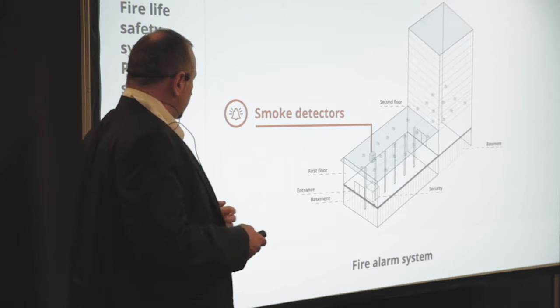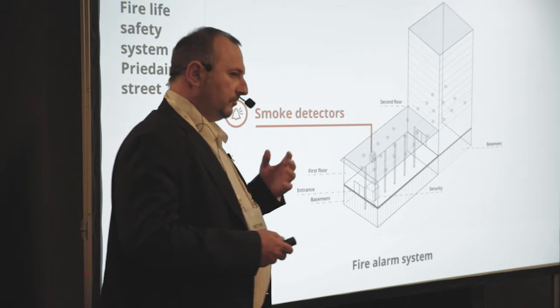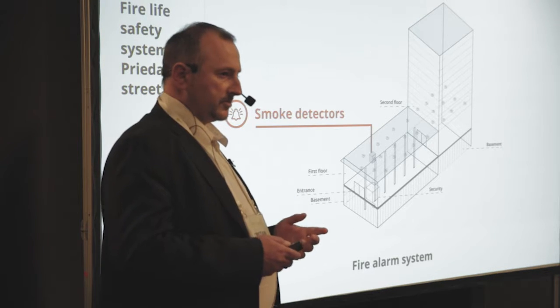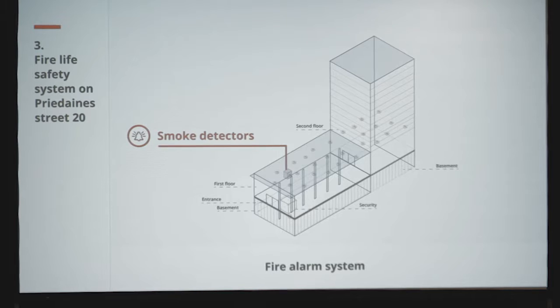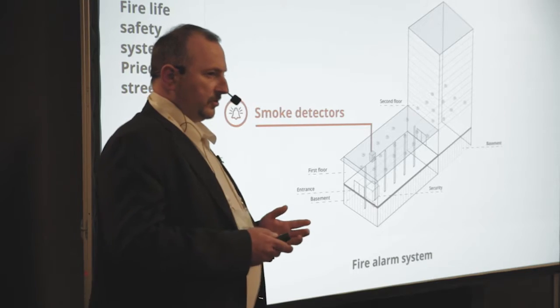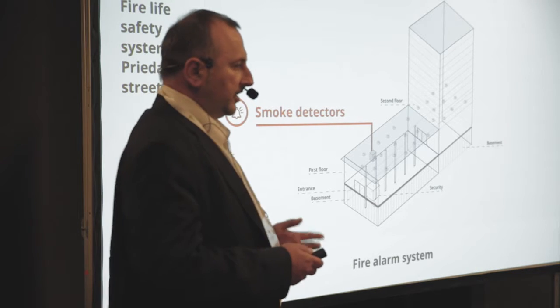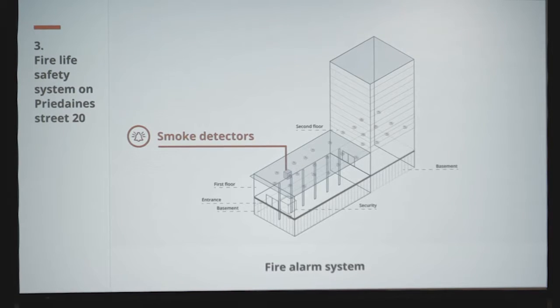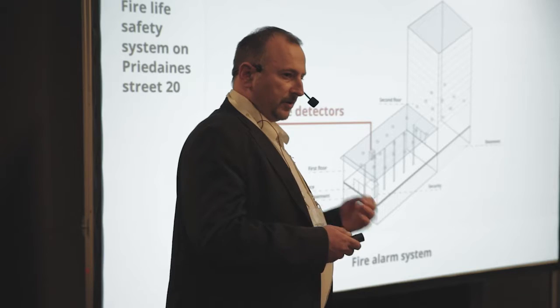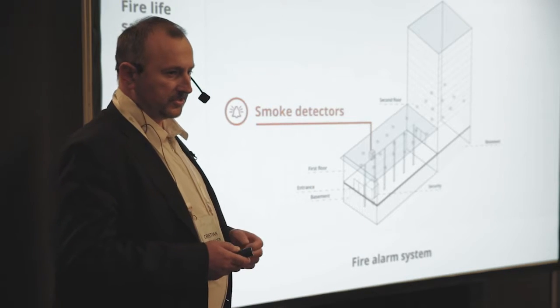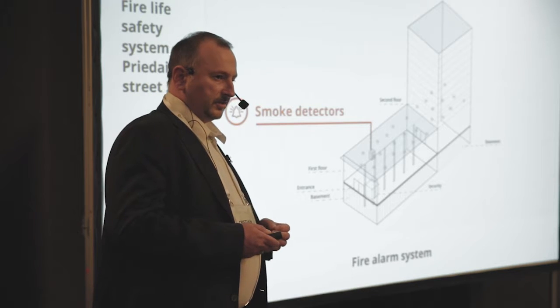The fire detecting system has manual detectors with push buttons, which are mounted at entrances and evacuation doors. If someone locates a fire, then he presses the push button and the fire alarm goes strictly to the fire control panel, and that is absolutely in the second mode.